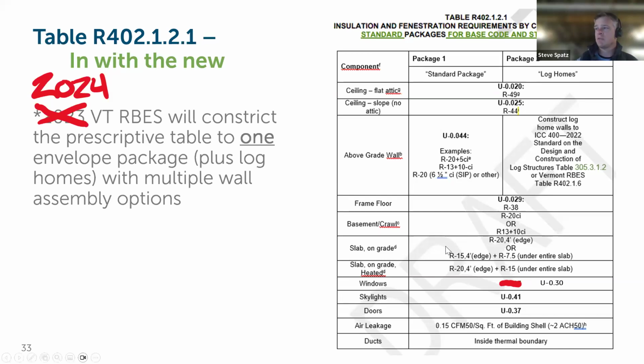Some other changes that are significant from the 2020 prescriptive values are slab insulation values are increasing to R20. So slabs on grade and or heated slabs are now going to need to meet R20 rather than R15. Window U values are at 0.30. There was initial debate about moving to triple pane windows for performance, but the maximum U value requirement, minimum performance requirement for windows is a 0.30 U value. And one of the points options in the point side of this is iterating towards higher performing windows and moving towards triple pane.